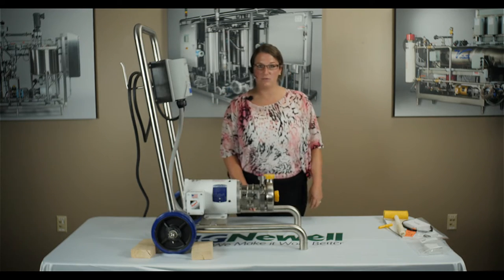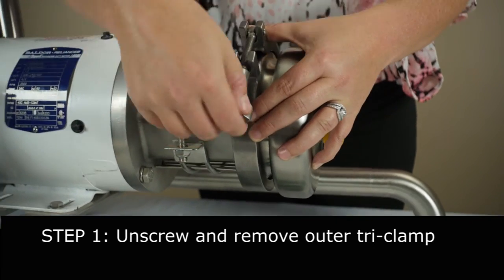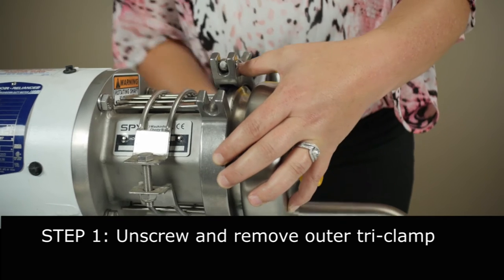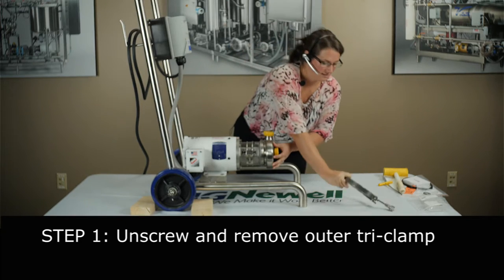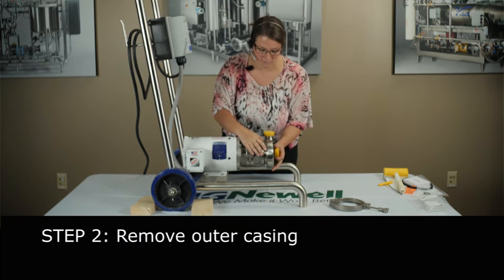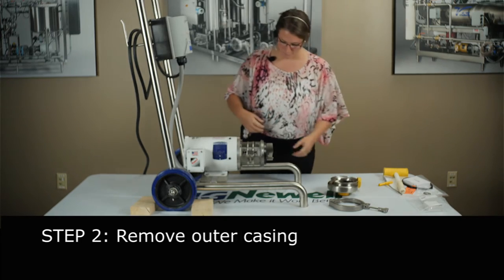First thing you're going to want to do to change your seals is take off this casing clamp — unscrew your wing nut, remove the casing clamp. Then you're going to remove your casing, and you might have to pull with a little force on these little C114 pumps. That's why you want to chock your wheels so you don't pull your pump across the brewery.